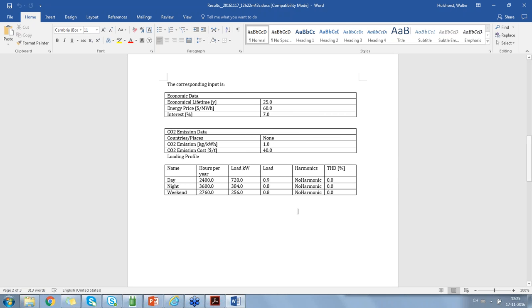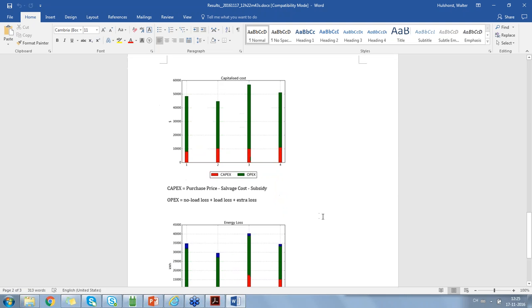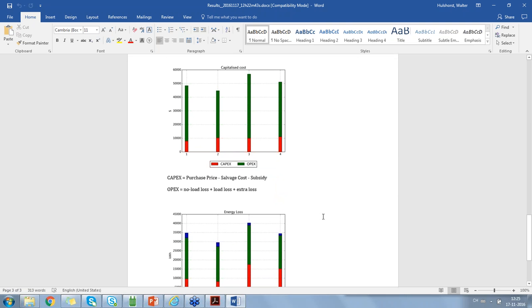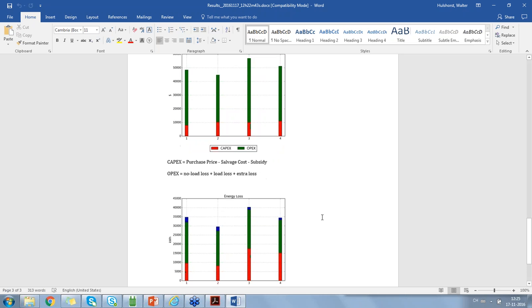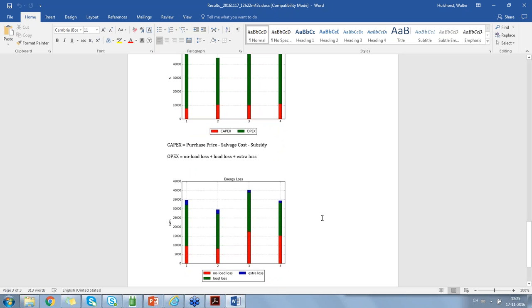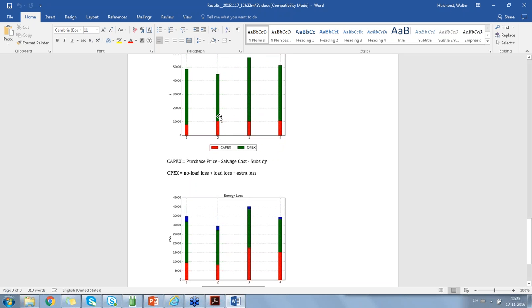This is just the corresponding input we have provided to the transformer. That's the next slide, so you can always find out what kind of inputs you have had. And the last slide is showing you some figures. The capitalized costs of the transformer is the above one, and the figure below is the total energy losses. And in this case, you will see that transformer 2 is the most economic transformer during the lifetime, despite the fact that it was more expensive than transformer number 1.